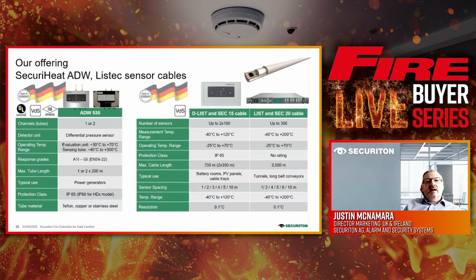I mentioned our linear heat offering briefly. The ADW on the left-hand side is the solid tube, either copper, steel, or Teflon tube. It's actually a pressure reading. We sense the pressure and relate that into a temperature reading to provide an alarm if there's been a temperature increase or indeed decrease in a particular area. That may be very useful in a slightly dirtier, hotter environment, let's say like a power generation area.